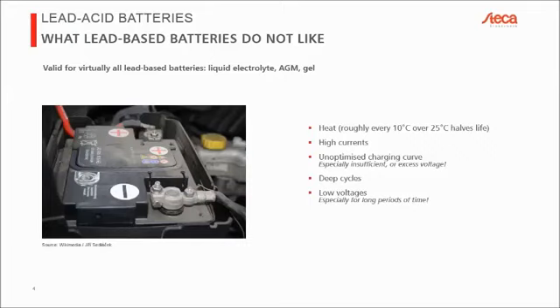In these charts, if you look closely, you'll find that typically for every 10 degrees Celsius above 20 or 25 degrees, you halve the life expectancy in terms of cyclability. So your battery might last 1,000 cycles at 25 degrees Celsius, but only 500 cycles at 35 degrees Celsius. Heat is, even if you otherwise treat your battery well, one of the most serious long-term effects in reducing the life expectancy of a lead-acid battery.